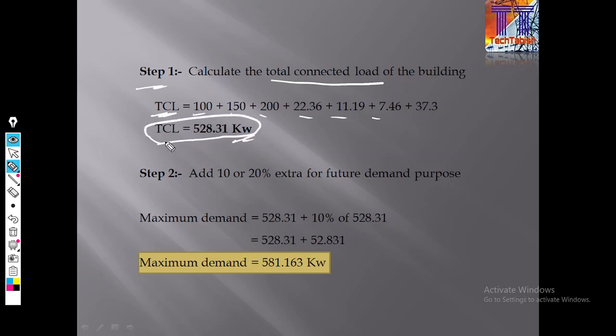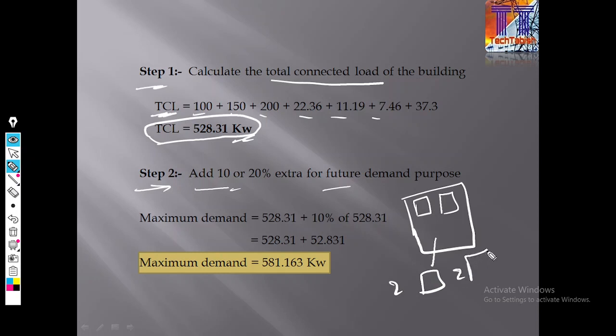Okay, now the step 2. In step 2 what we are seeing, add 10 to 20% extra for the future demand. Like we have a building, we have limited load now, while at the time of construction we know these are the limited demand, but in future if we increase, like if we add 2 fridge or 2 washing machine extra, so for that we have to think earlier at the time of designing. So 10 to 20%, that is for the future demand purpose.